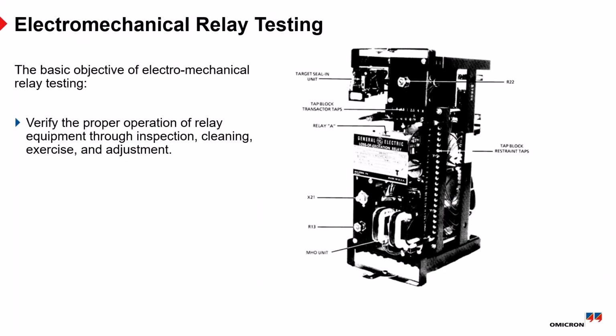Basic objective of electromechanical relay testing: verify proper operation of relay equipment through inspection, cleaning, exercise, and adjustment. I can admit that when I started in the business, we were doing a fair number of these. There's obviously a pickup test, so you apply a stimulus and measure the point at which the mechanism begins to operate. Then we had a timing test where you made a pre-fault condition and made a step change in input and measured the amount of time it takes for the relay to respond. Those are the basic tests that we would run on all devices.